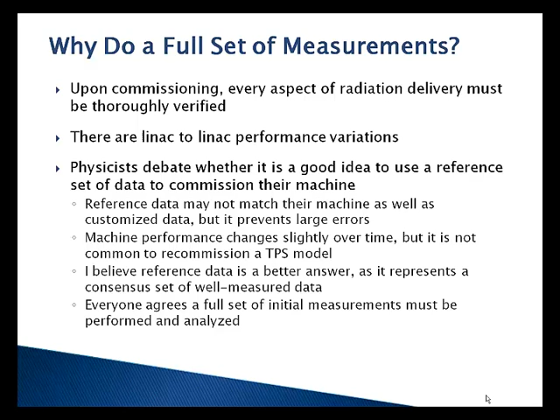I personally really like reference data because it removes a large error source out of the equation. That doesn't mean that you don't measure your machine as if you did not have reference data, but use reference data and compare everything to it. This is my particular choice. Now, we don't always have that option. So what are measurement problems that we see? Water tank scan settings are mislabeled. The water tank setup was incorrect. We didn't use the right detector to measure the right things.